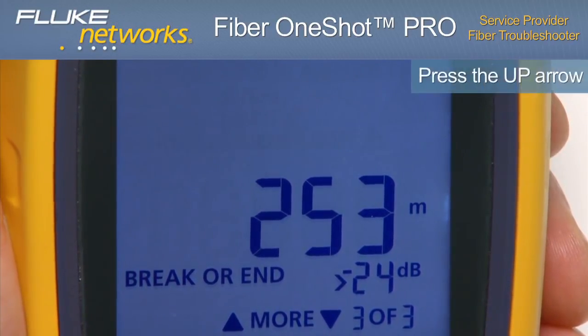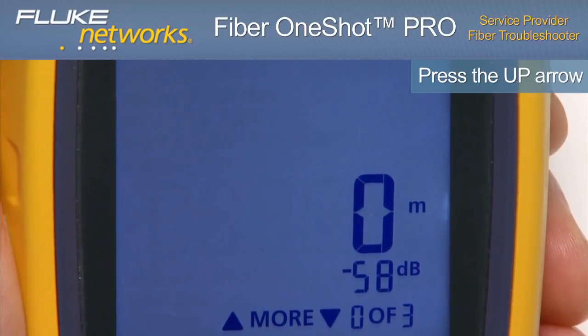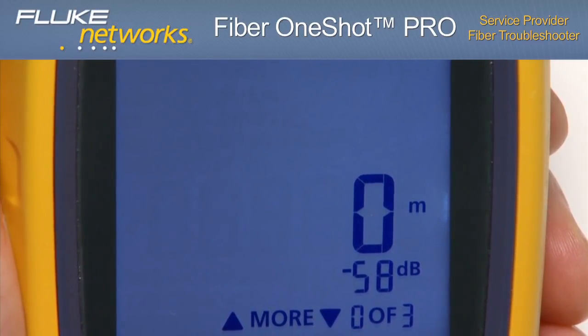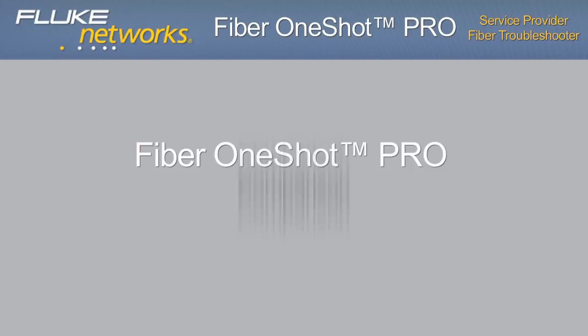If the up arrow is pressed once more, you'll notice event 0 of 3 is displayed. This indicates connection to the troubleshooter, but could also indicate no fiber is attached or that the connector is dirty if this is the only event shown.